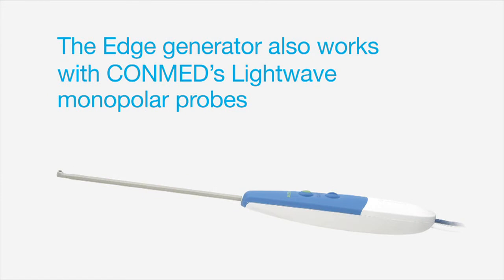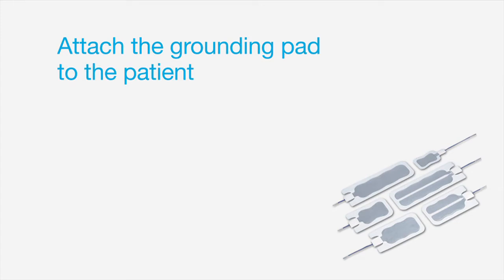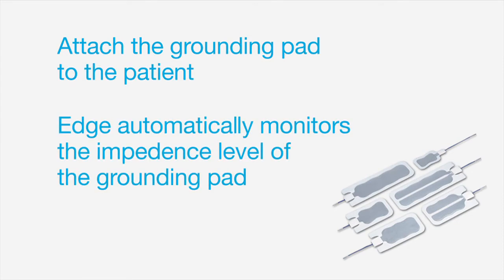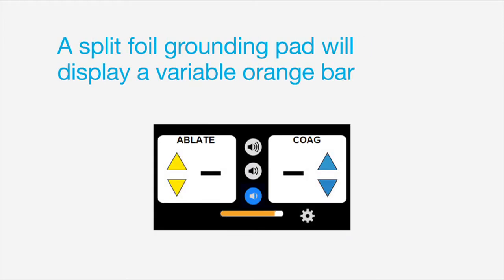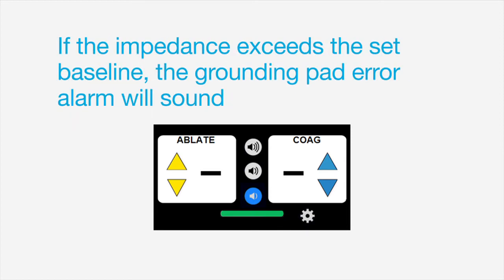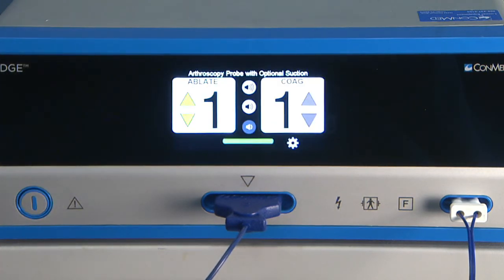The Edge generator also works with ConMed's Light Wave monopolar probes. To install a monopolar probe, insert the grounding pad connector, then attach the grounding pad to the patient. Edge automatically monitors the impedance level of the grounding pad. A single-foil grounding pad will display a full green bar. A split-foil grounding pad will display a variable orange bar that fluctuates based on the impedance level. Touching the orange bar will set the baseline for impedance, which changes the bar color to green. If the impedance exceeds the set baseline, the grounding pad error alarm will sound. To complete monopolar probe installation, select the type of probe installed from the touch screen. The probe type will appear on the home screen to indicate a successful connection.